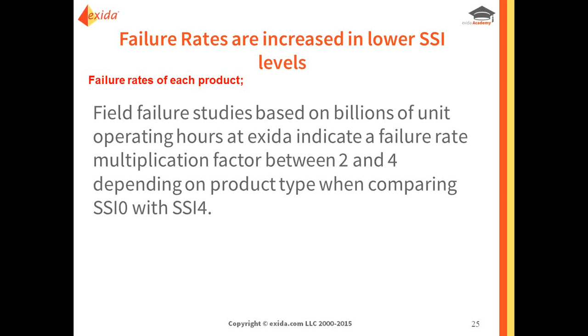So, field failures of each product. Well, field failure studies based on billions of unit operating hours at exida indicate a failure rate multiplication factor between 2 and 4 from site to site, depending on the product type. So some are more variant than others, and like I said, it's the importance of that product. If it needs to be checked all the time, or if it doesn't need to be checked all the time, then maybe you will see a high multiplication factor. And this is basically comparing between an SSI 0 and an SSI 4.